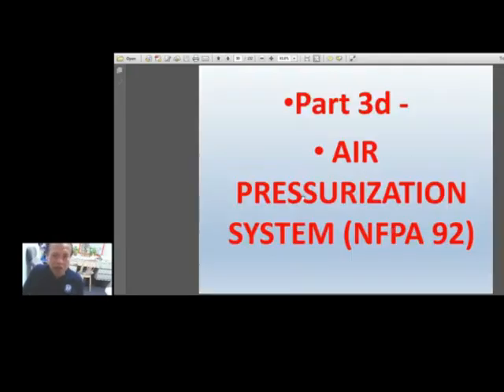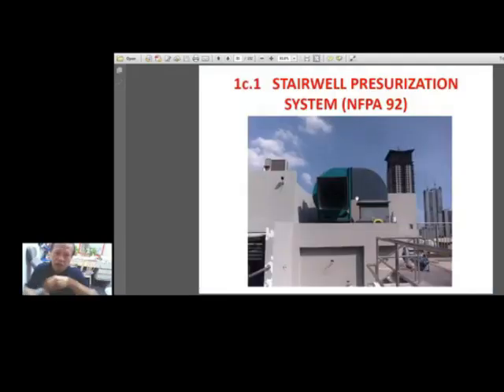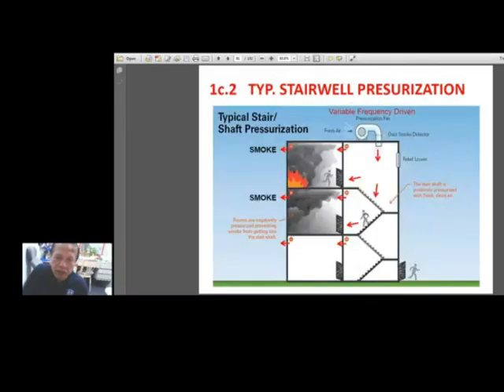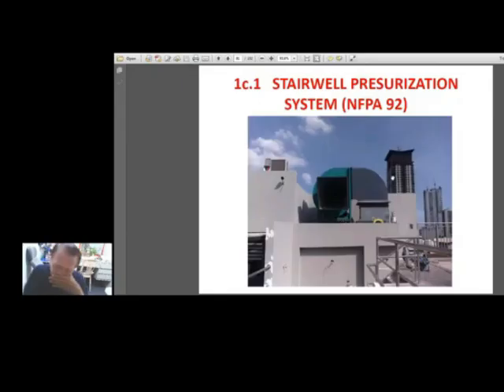Now we proceed with the next topic, air pressurization. The fire exits must be assured to be safe for people to run through, to exit through, in order that the people who will be running for their safety to the fire exits will have a greater chance of not being suffocated. No? So here is a picture of a stairwell fan. A pressurization fan. It's not an exhaust fan. It is a fan that would get fresh air from outside of the building and put it inside the stairwell, at the top of the stairwell.